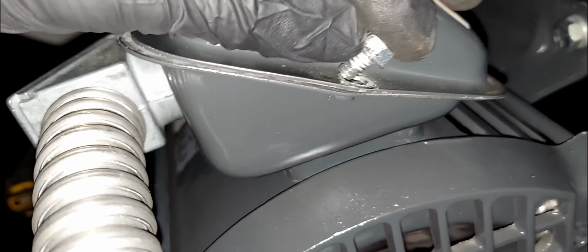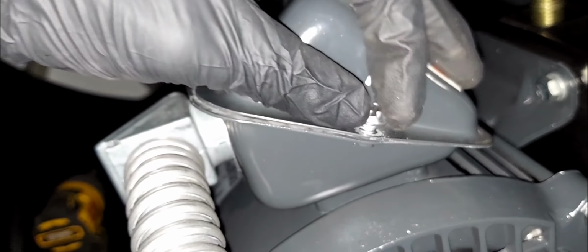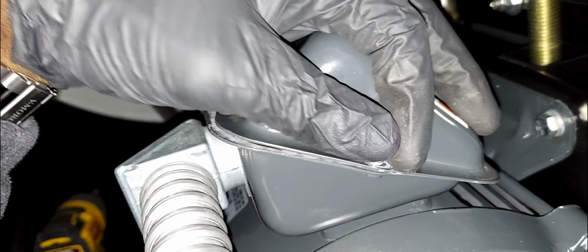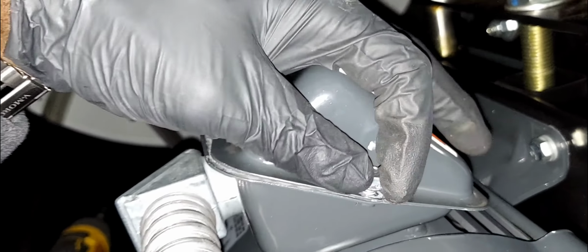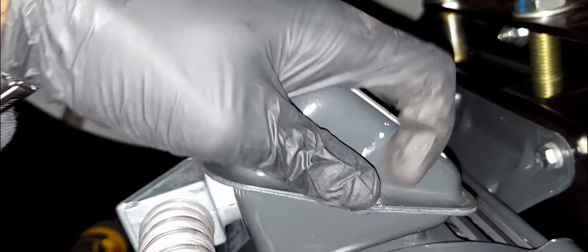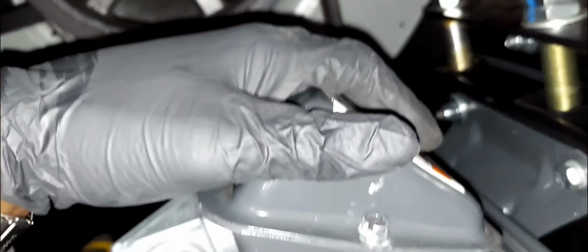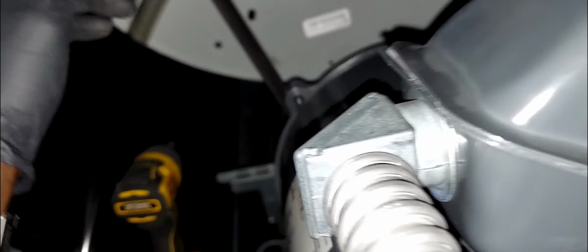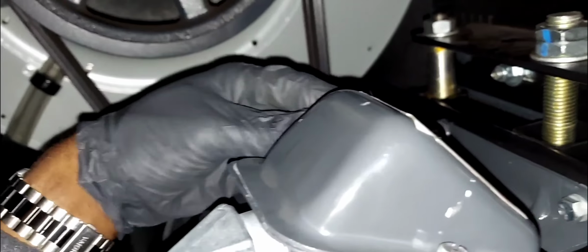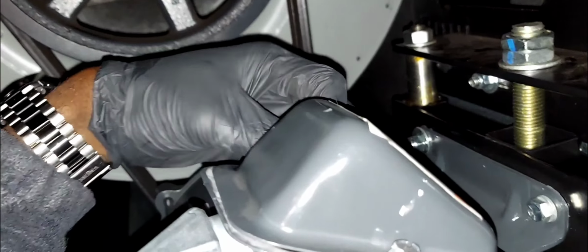But like I said, before I do that, I want to make sure I ohm the motor out, make sure there's no ground fault, nothing grounded on the motor windings. I won't use a meg tester or megohmmeter. I'll just use my regular ohmmeter and just check for ground and that the windings have continuity, and then I'm just going to reset it and then check the amperage. I'm going to match the amperage of the nameplate versus what it's drawing.